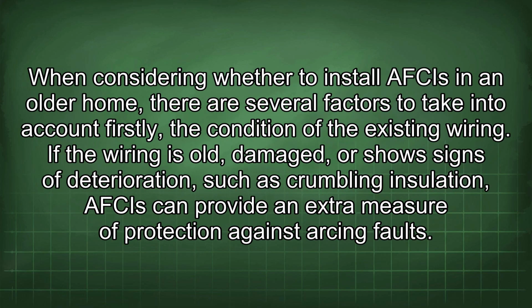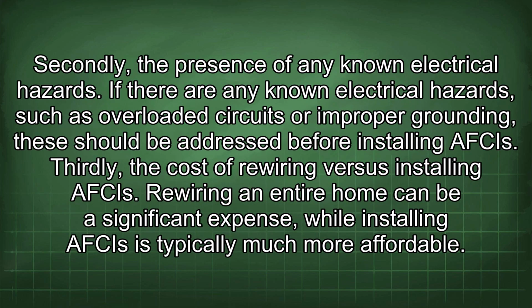of fire. When considering whether to install AFCIs in an older home, there are several factors to take into account. Firstly, the condition of the existing wiring. If the wiring is old, damaged, or shows signs of deterioration, such as crumbling insulation, AFCIs can provide an extra measure of protection against arcing faults. Secondly, the presence of any known electrical hazards. If there are any known electrical hazards, such as overloaded circuits or improper grounding, these should be addressed before installing AFCIs. Thirdly, the cost of rewiring versus installing AFCIs.